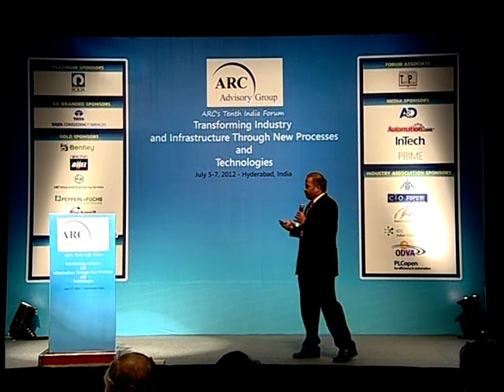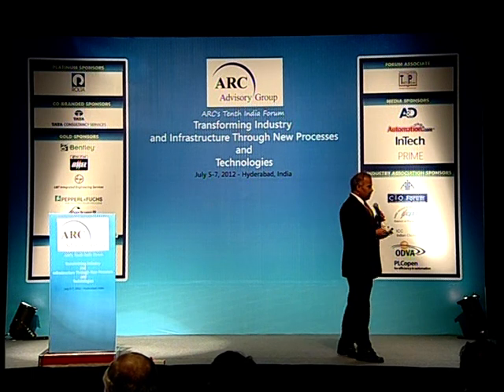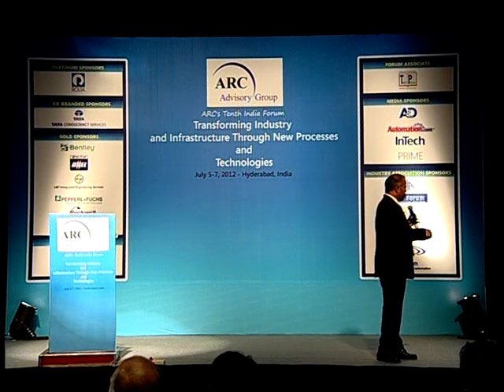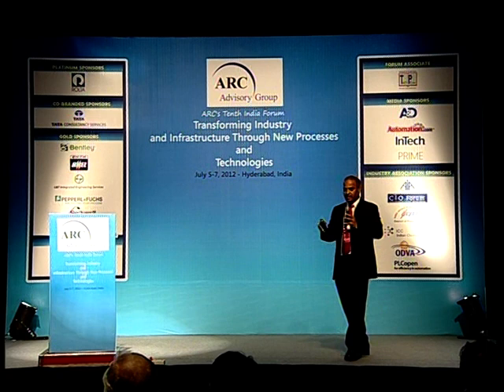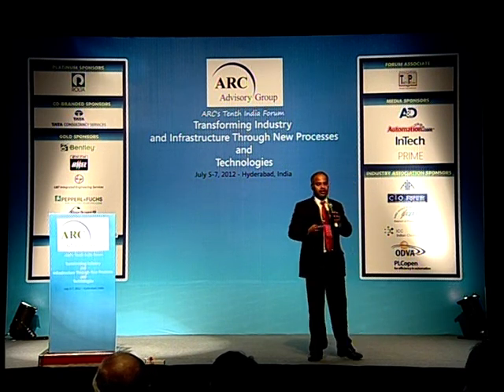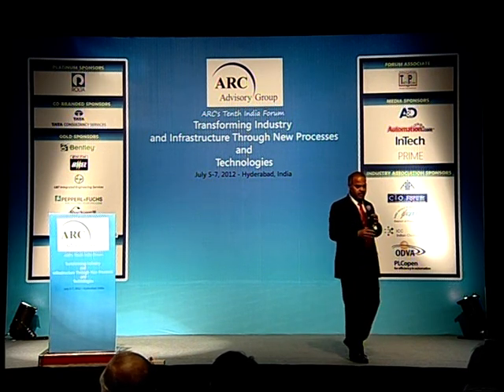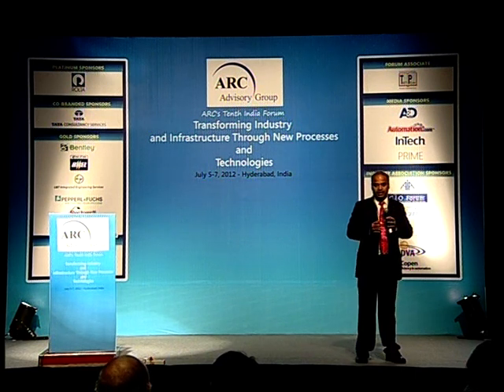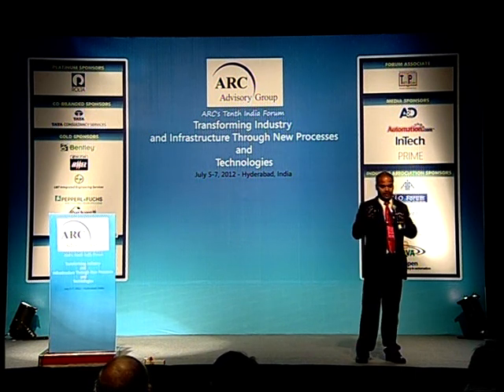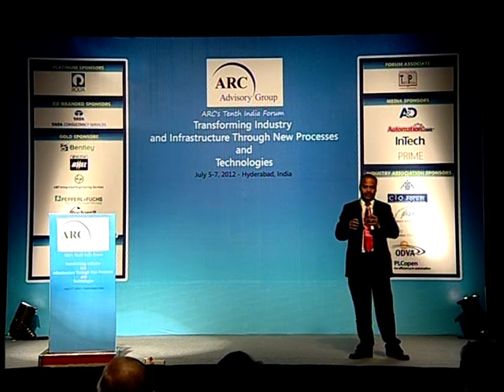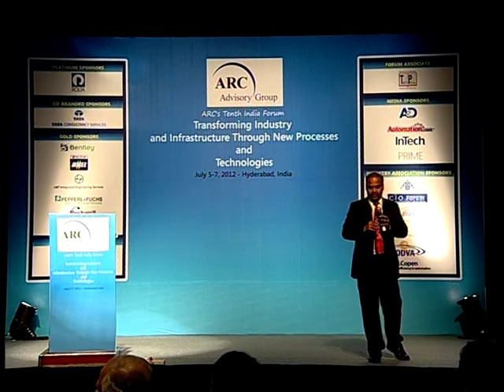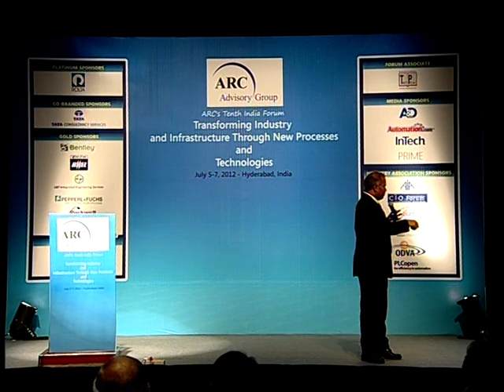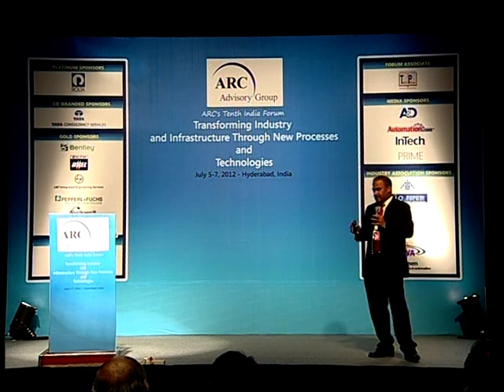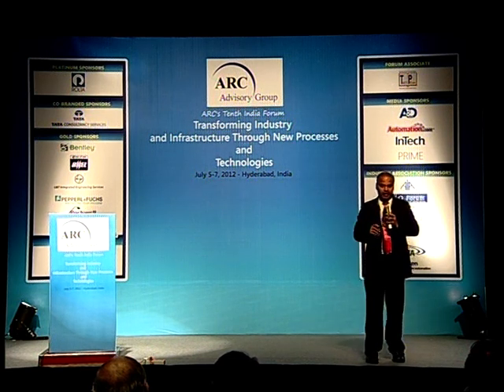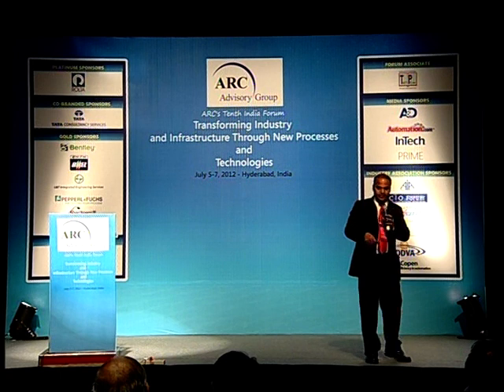There are different ways we can limit the energy that is going inside the hazardous area. One method is called flame-proof. If it is a high-power device, the only way we can limit is to let the energy go all the way to the hazardous area, and we contain the explosion. Even if something happens, for example an explosion or spark or whatever it is, we are not going to let it come out of the enclosure. That's the way we do this in flame-proof. And we have some other methods. One of the least expensive and simplest to realize is called intrinsically safe.